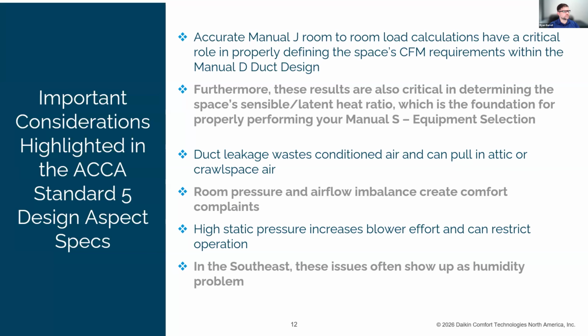So, important considerations highlighted in our Standard 5. Manual J room-to-room load calculations have a critical role in properly defining the space's CFM requirements within your Manual D duct design. So if you get that wrong, everything is going to end up being wrong, because those results are also a critical piece in determining your sensible-latent heat split ratio. And then that's the foundation for forming your Manual S and selecting the appropriate equipment.